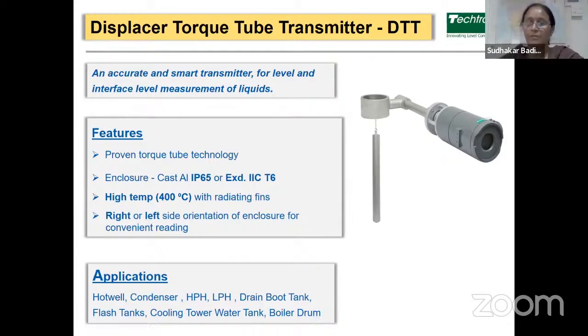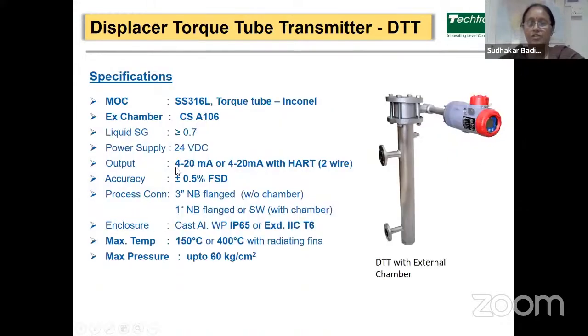Basically, this is suitable for high temperature and high pressure applications. So material will be available in SS316L and torque tube will be in Inconel. Then external chambers will be available in CSA106. The output of this transmitter is 4 to 20 milliampere or 4 to 20 milliampere with HART with a two wire connection. The accuracy of this transmitter is plus minus 0.5% of full scale deflection. It is suitable for maximum temperature of 150 degrees Celsius or 400 degrees Celsius with radiating fins and maximum pressure up to 60 kg per centimeter square.